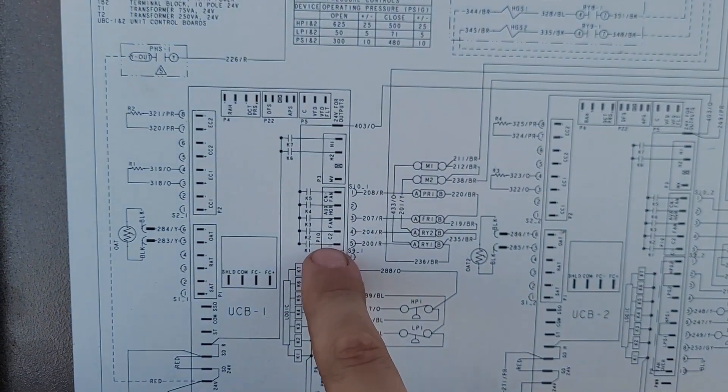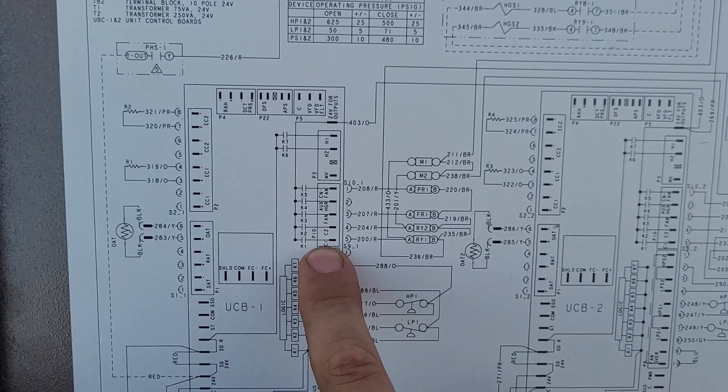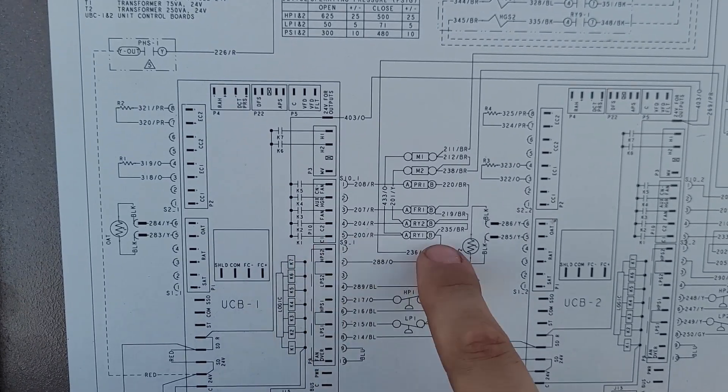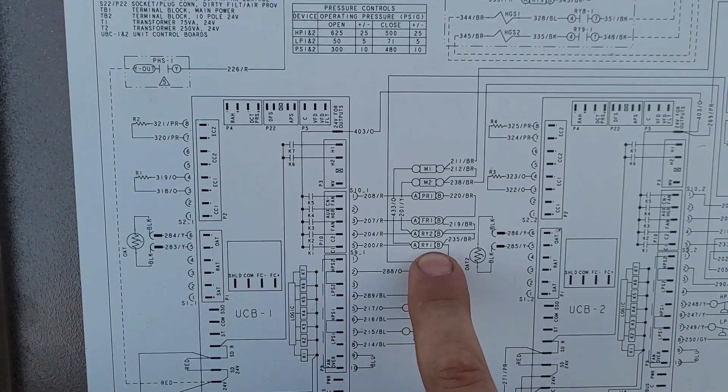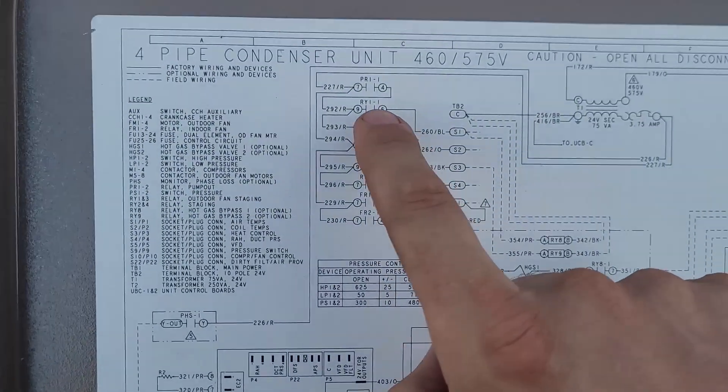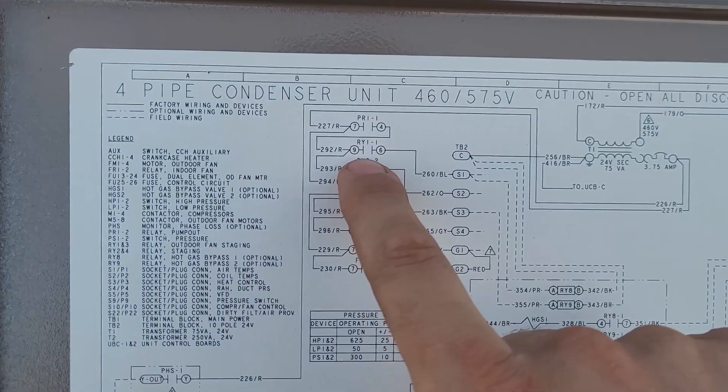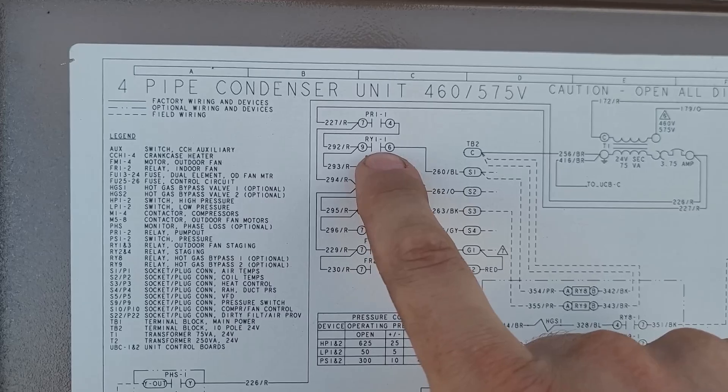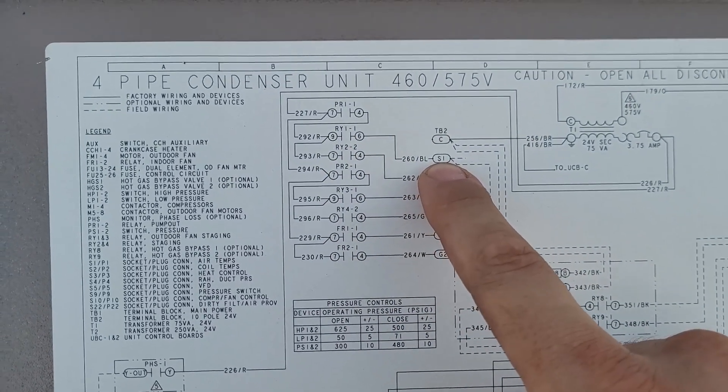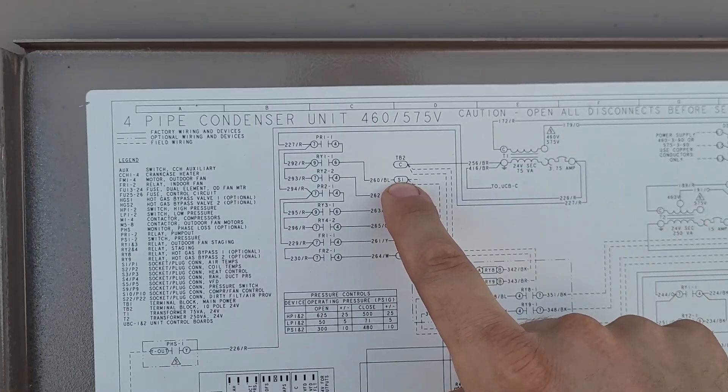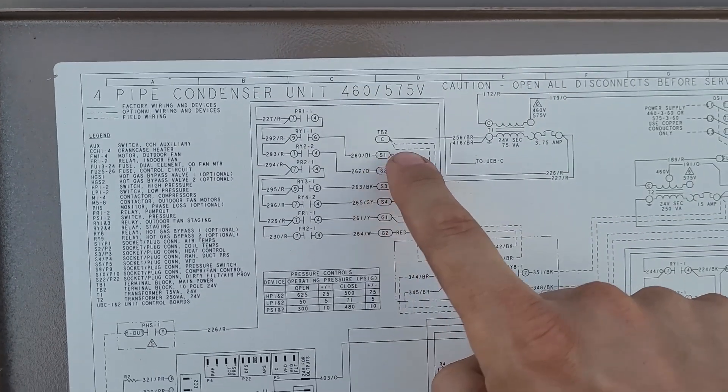So anytime the compressor is enabled, the RY1 relay is enabled, it makes the dry contact for RY1, sending 24 volts on S1.